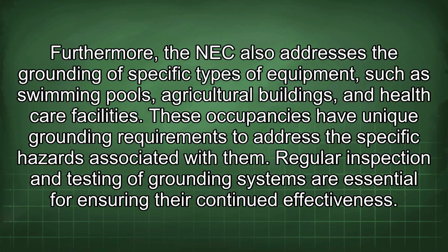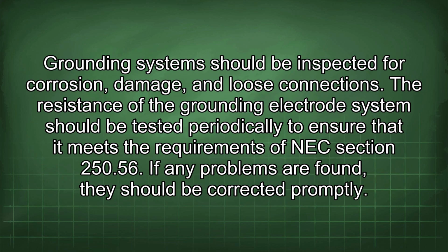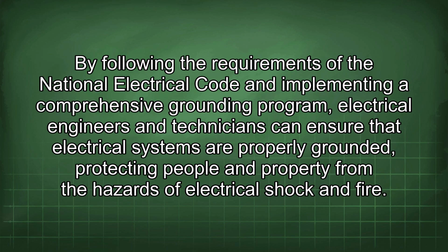Regular inspection and testing of grounding systems are essential for ensuring their continued effectiveness. Grounding systems should be inspected for corrosion, damage, and loose connections. The resistance of the grounding electrode system should be tested periodically to ensure that it meets the requirements of NEC Section 250.56. If any problems are found, they should be corrected promptly. By following the requirements of the National Electrical Code and implementing a comprehensive grounding program, electrical engineers and technicians can ensure that electrical systems are properly grounded, protecting people and property from the hazards of electrical shock and fire.